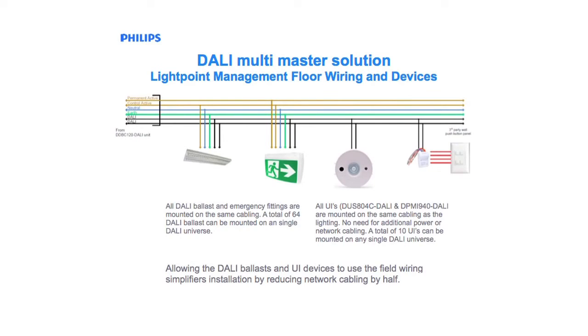Here we see how all the DALI devices are connected together in the field on the same wiring. A DALI ballast requires an active, neutral and earth for power. Running in parallel will also be the DALI figure 8 pair shown in black. DALI emergency fittings will have an additional permanent active, so the fitting is able to detect a loss in power and still be controlled.